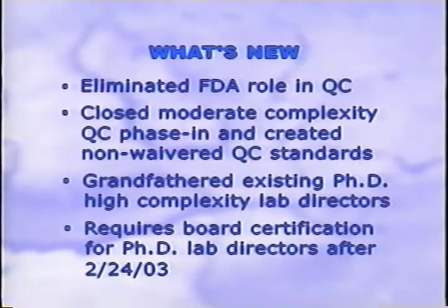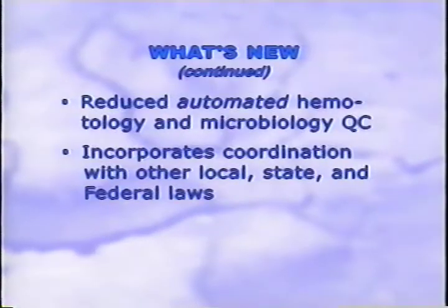We have closed the moderate complexity phase-in and created non-waived QC standards, that is, one set of standards for moderate and high complexity QC. We have grandfathered existing PhD or doctoral degree high complexity laboratory directors. We also are requiring, subsequent to February 24th, board certification for PhD laboratory directors. We have reduced quality control for automated hematology and microbiology. We have also incorporated coordination with other local, state, and federal laws.